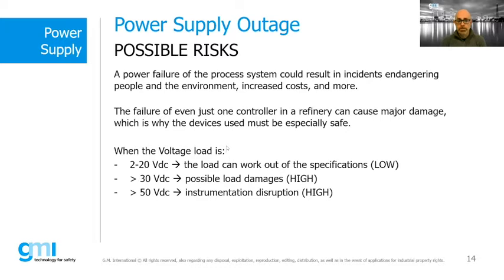Often we try to avoid this issue using redundancy, but we mistakenly think that two power supplies in parallel are sufficient to make us immune from possible faults in the power supply system. Redundancy cannot solve this on its own and cannot guarantee us immunity from power supply failure, because a standard power supply system does not take into account the common mode faults that can afflict standard power supplies. These common mode faults can cause spurious system faults with their related production downtime, which will significantly affect cost. The redundancy of a safety power supply minimizes this risk because common mode failures are considered in the SIF calculation necessary to get the certification for a safety-related device.